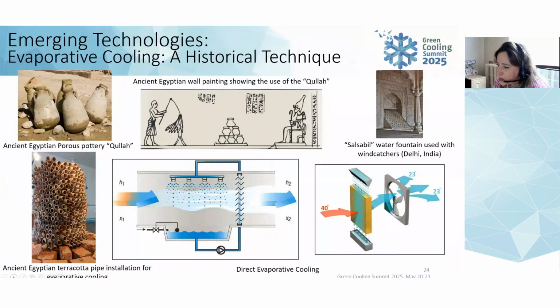Evaporative cooling, Marco was speaking about this. I believe I cannot introduce it better than he did. It's another passive cooling technology, a historical technique also, which provides comfort cooling. It's called adiabatic cooling, as only heat exchange happens between the air and the water. In very simple words, the process is about introducing water directly into the outdoor filtered air stream, in this middle figure I'm showing here, through a spray system or a saturated wetted pad, as in the figures in the corner and on the right. The hot and dry air stream provides the heat for the water.